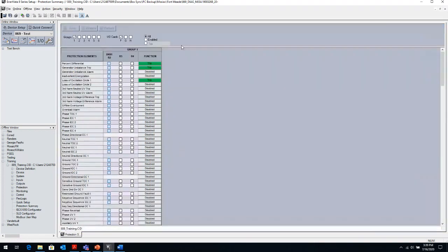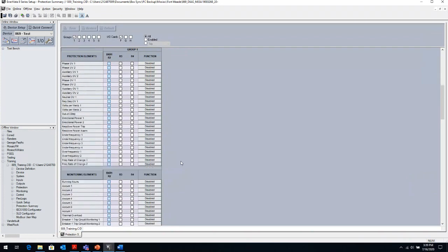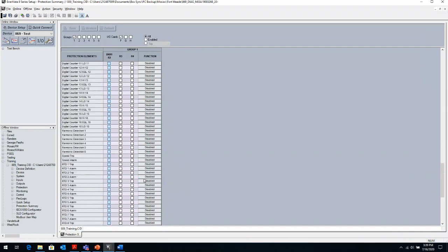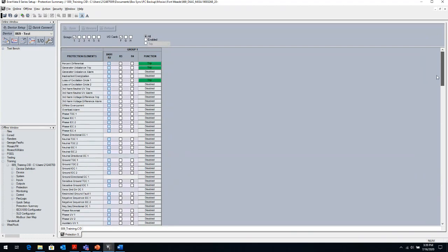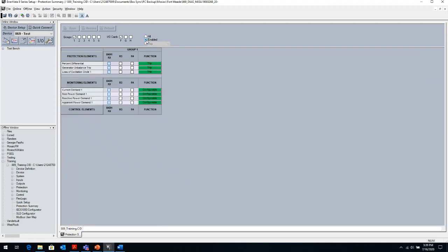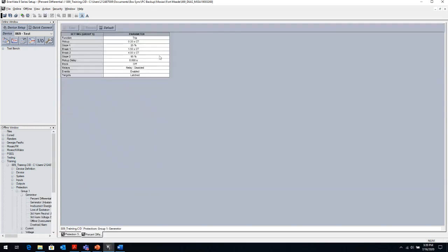And the protection summary will show me all of the available elements in the relay, all the protection as well as monitoring and control elements. If I'm setting up the relay, then I can click on these elements and set them up. Or if I'm looking at the setting and I just want to see what's enabled, I click on enabled, and it will only show me the elements that are enabled. In this case, the percent differential, as we saw previously from the quick setup screen. I click on it, and it will take me to the settings of the differential protection.